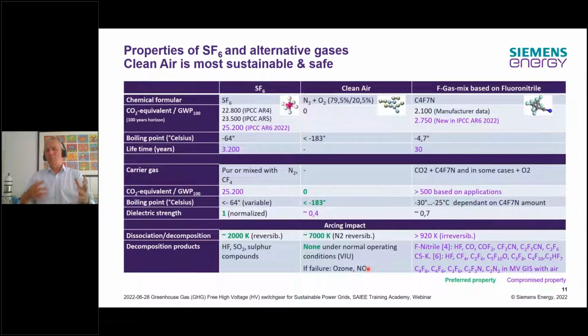So actually, it's the clean air, or synthetic air, as we also call it. It's the best solution sustainability-wise, which can be used. We did lots of research, more than 500 gases we looked at, and the second best from our perspective are the so-called F-gas mixes based on fluornitrile. You see here, it's also a strong greenhouse gas, 2,700 times stronger than CO2. It has a boiling point of -4, which means that at lower temperature it liquefies. And also it has a lifetime of 30 years.